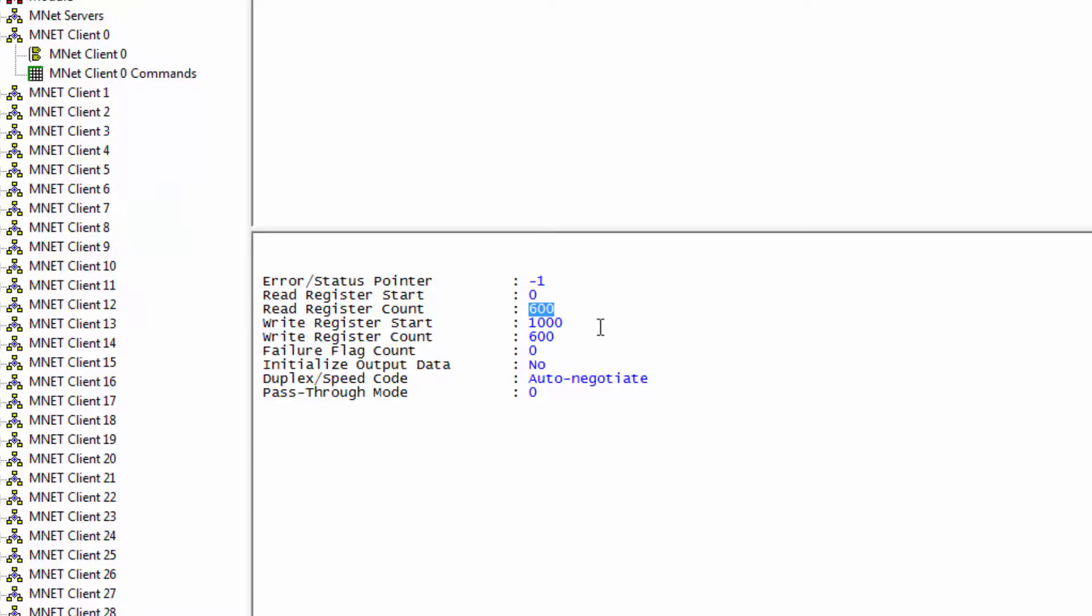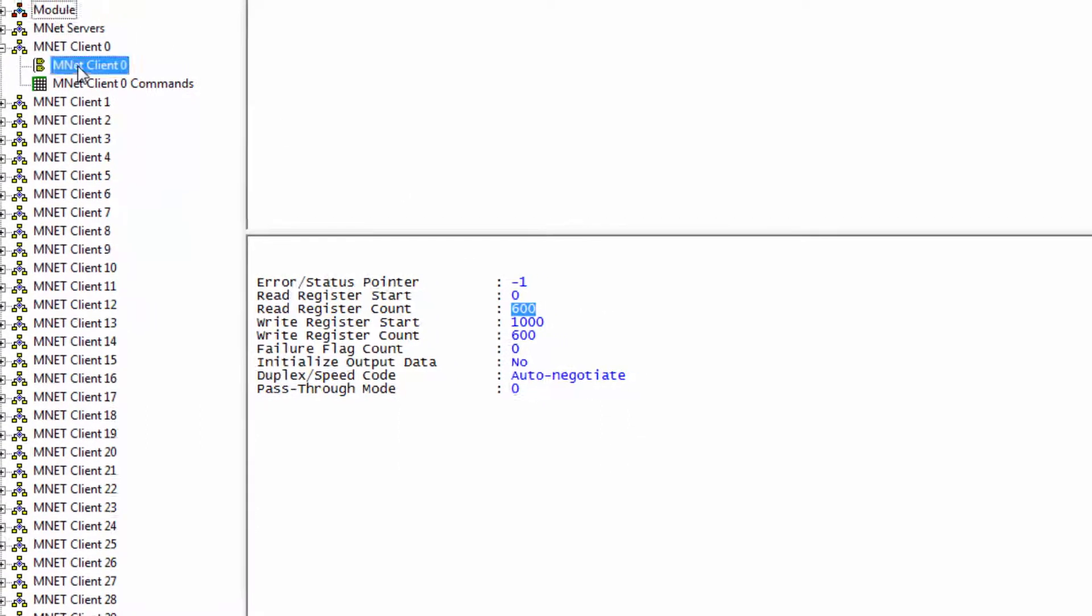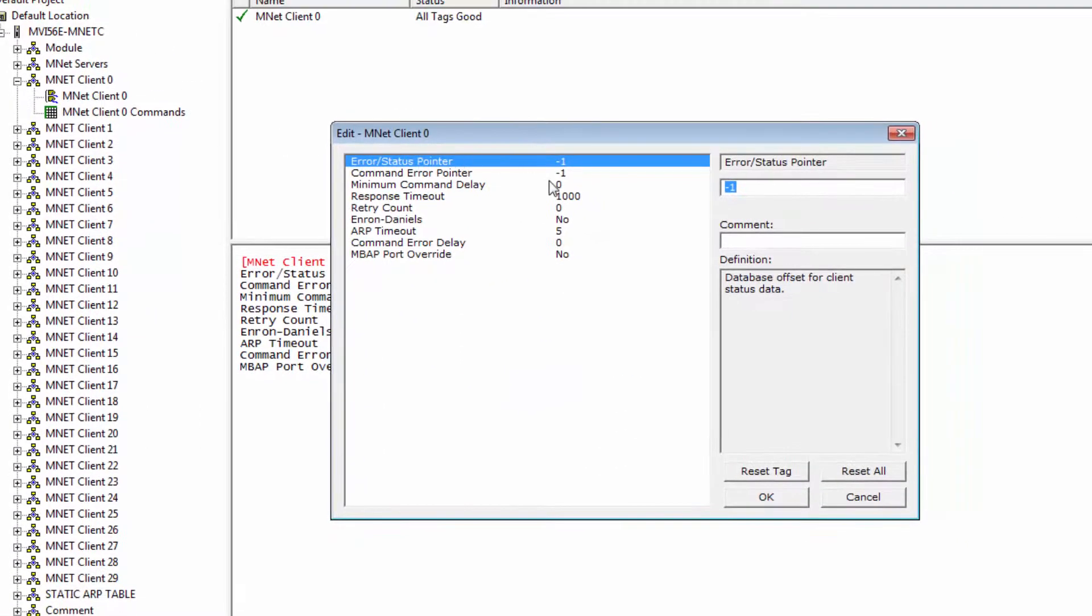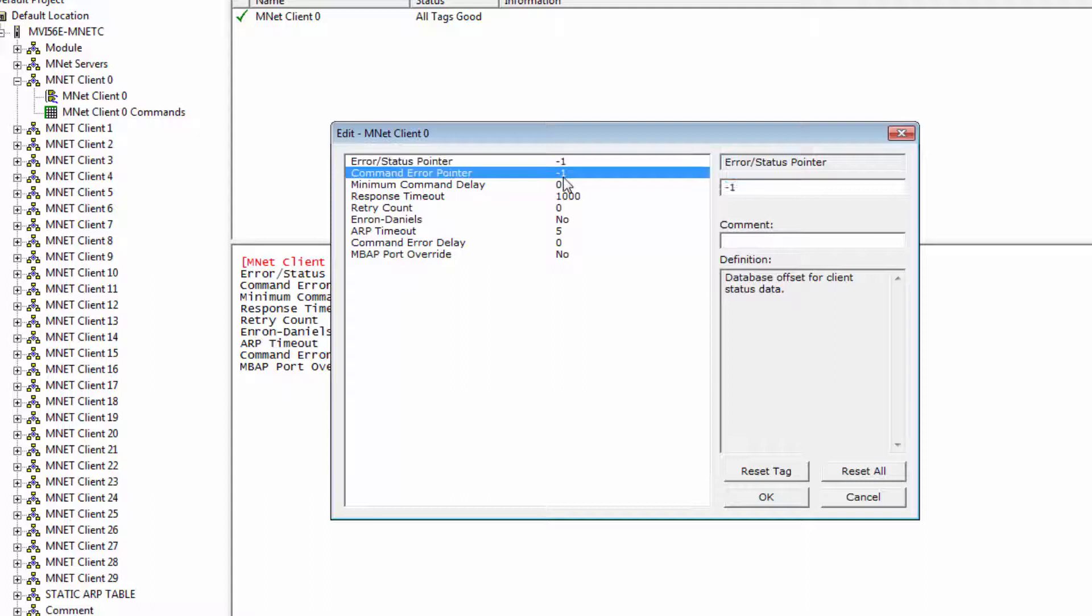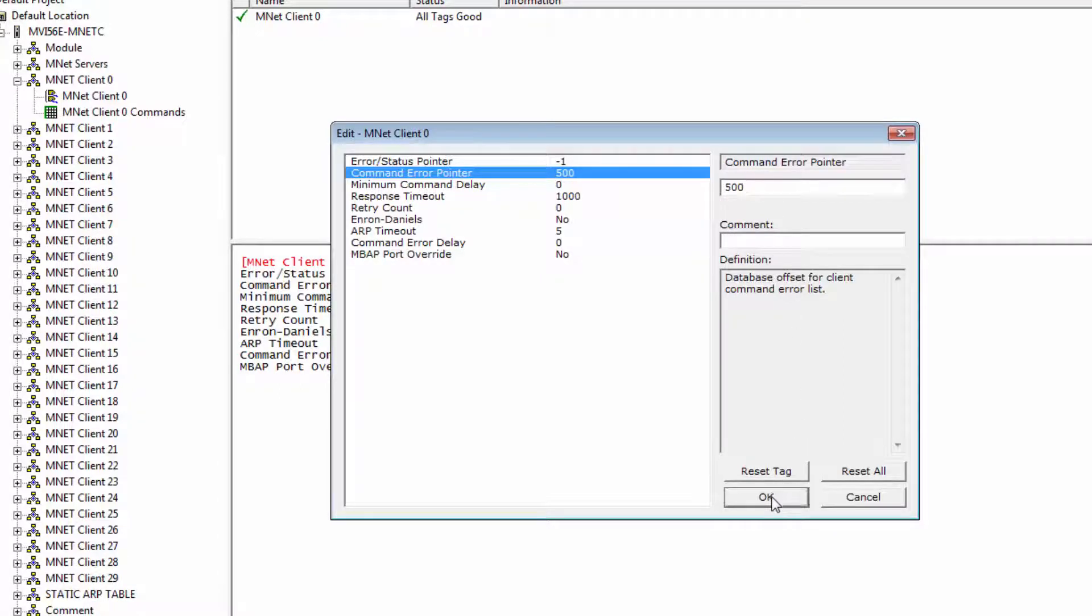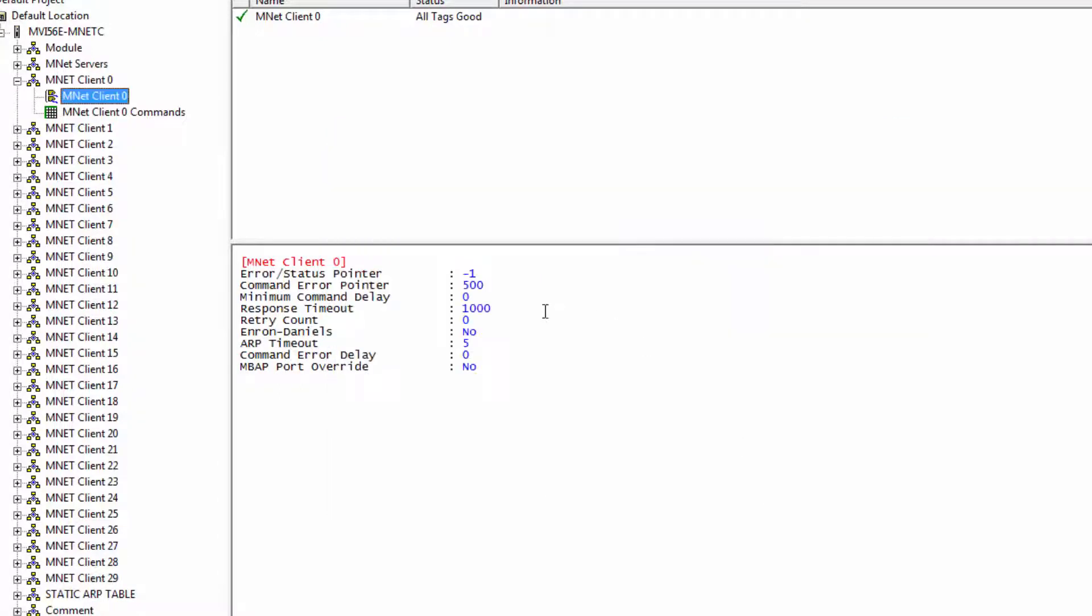So if I were to set the Command Error Pointer to 500 for Client 0, error data will then be placed into the Read 500 address. This will give me a hundred registers to work with and it will be available to the program.